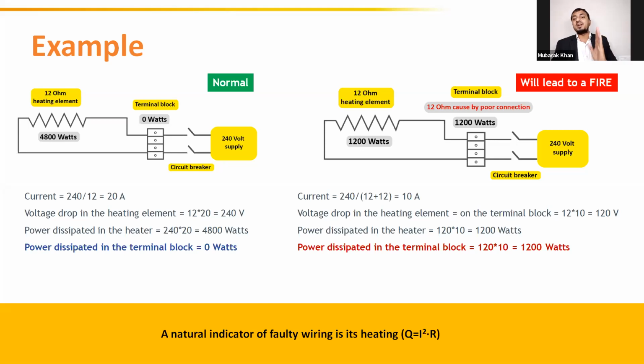Now, if there is an abnormality in the circuit and there is a loose connection at the terminal block, and for simplicity we have assumed that the magnitude of the loose connection in terms of resistance is around 12 ohms. Under that scenario, when the 240 volt power supply tries to feed the circuit, there will be two resistances coming into the picture. One resistance is because of the terminal block, and the second resistance will be because of the heating element.